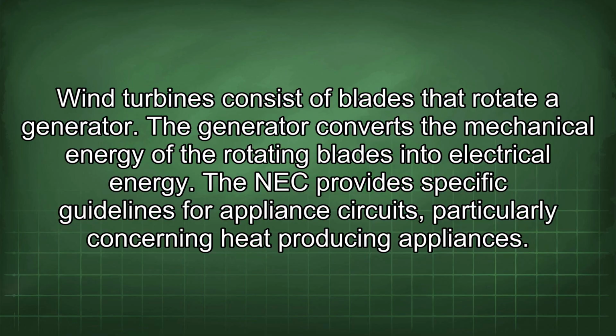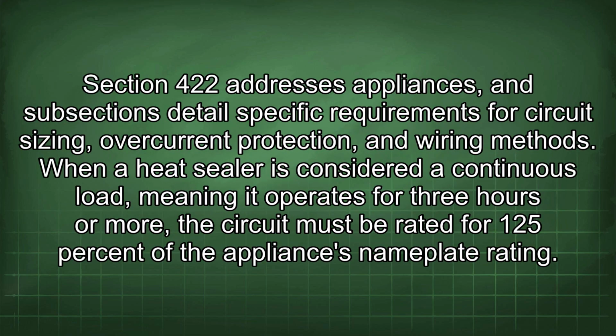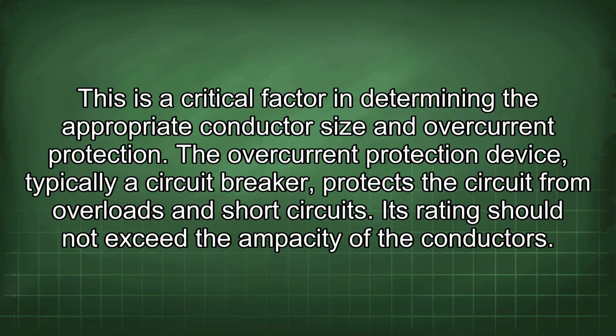The NEC provides specific guidelines for appliance circuits, particularly concerning heat-producing appliances. Section 422 addresses appliances, and subsections detail specific requirements for circuit sizing, overcurrent protection, and wiring methods. When a heat sealer is considered a continuous load, meaning it operates for 3 hours or more, the circuit must be rated for 125% of the appliance's nameplate rating. This is a critical factor in determining the appropriate conductor size and overcurrent protection.